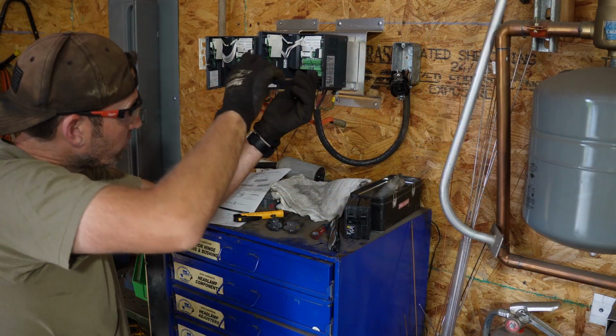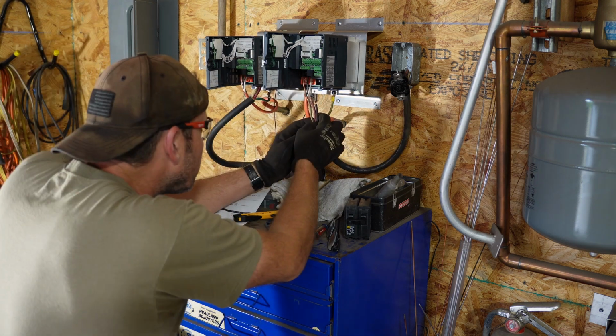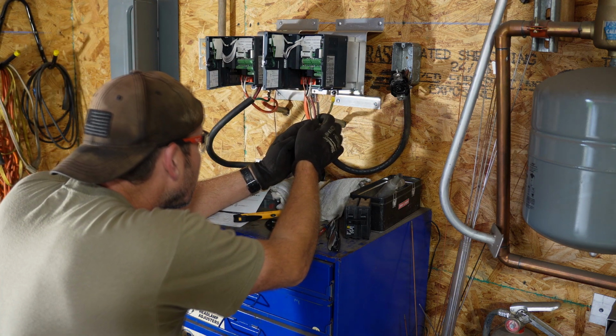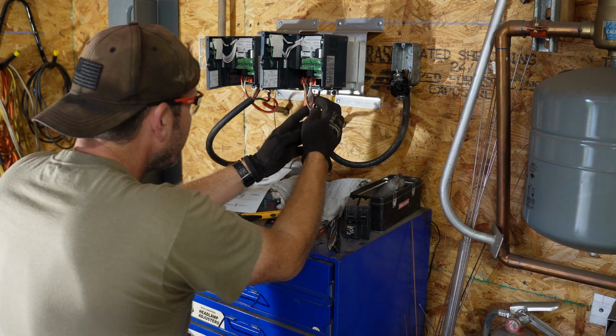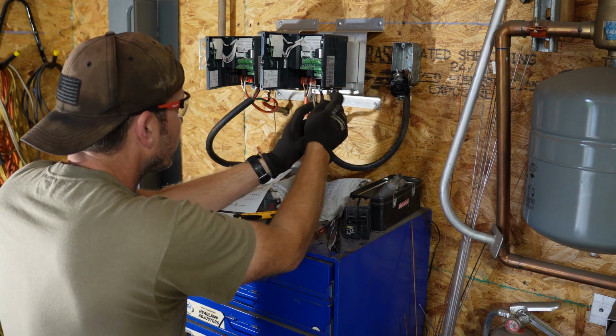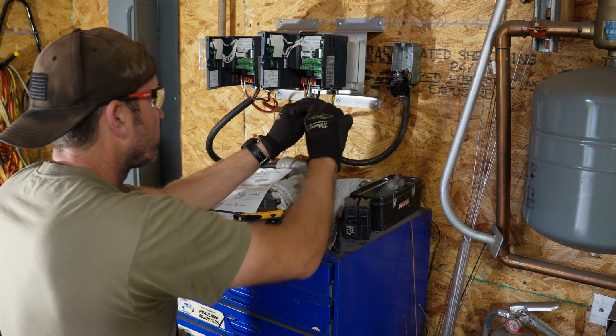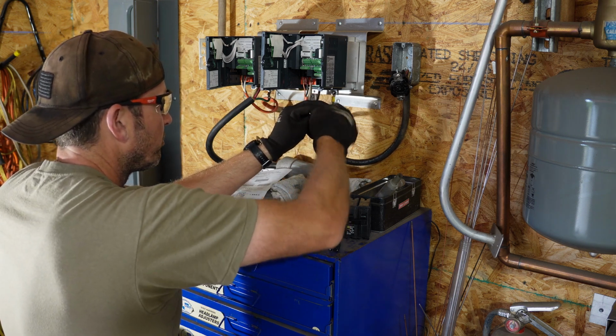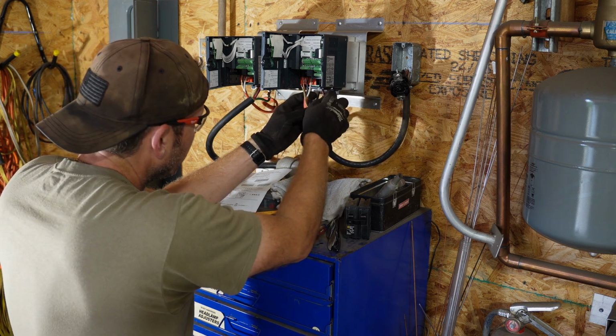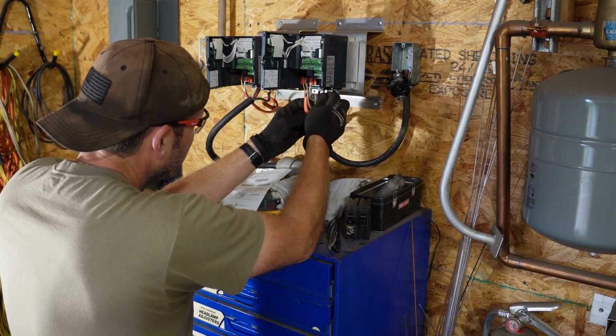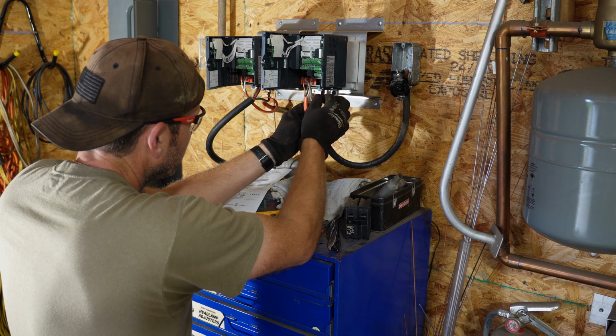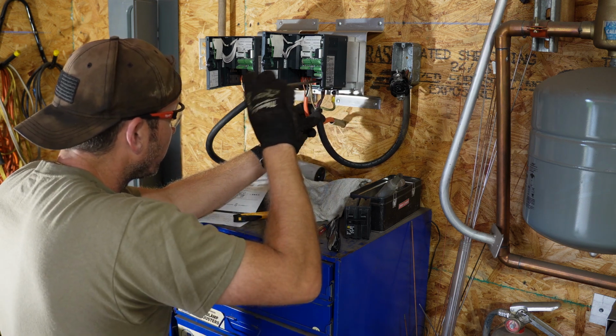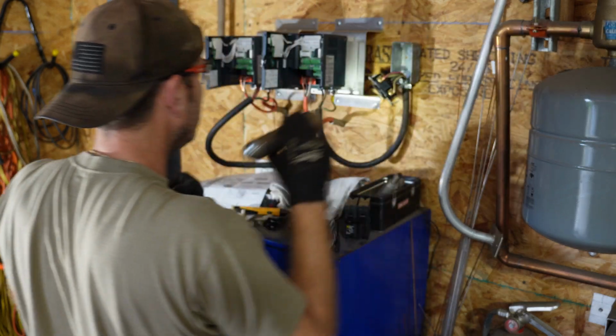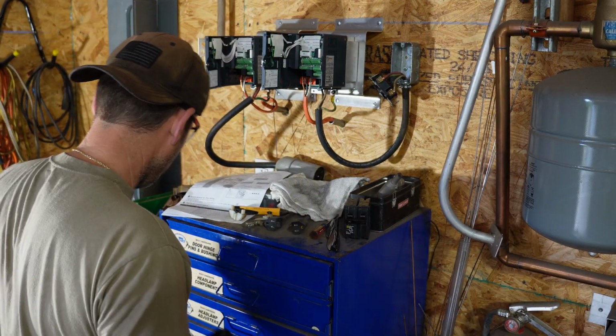But I'm going to go black, red, then white. So T1, T2, T3 is the same as U, V, and W. So we'll go black to U. I'm using 12 gauge stranded wire, which should be more than enough for the 10 amps or so of current, anywhere from 8 to 10. I think 12 gauge is usually rated for upwards of 20 amps, so this should be plenty thick enough wire. And a Y - all right, so we'll go X, Y, Z for black, red, white on both.